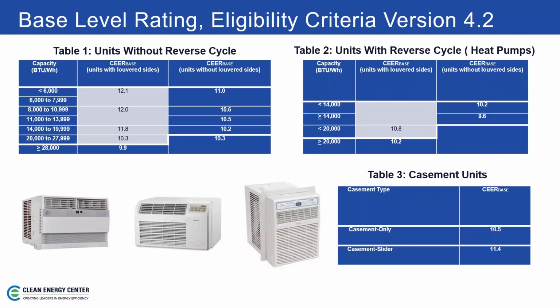So you can see, if you look at table 1, we have the CEER base, and these are the units with louvered sides. So that would be your typical through the window air conditioner. And you can see also, based on the BTU ratings over here on this side, the CEER requirement changes. So you just want to be aware when you're out there searching, when you decide what size you want to install, that you're matching the right BTU unit up to the right CEER level. And then CEER base over here in this column are units without louvered sides, or those through the wall units. And you can see that their CEER base is slightly lower, okay?